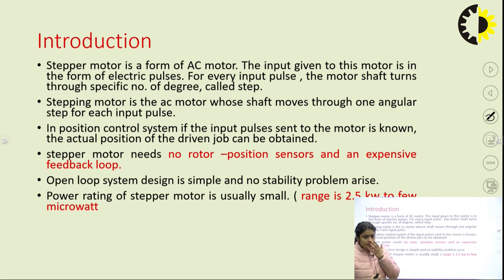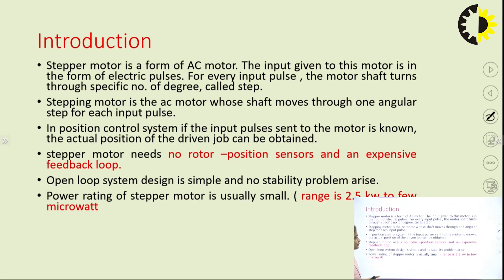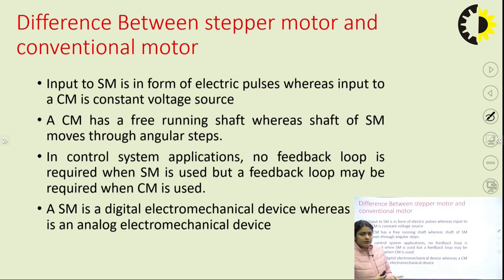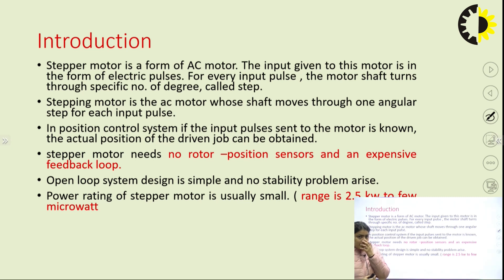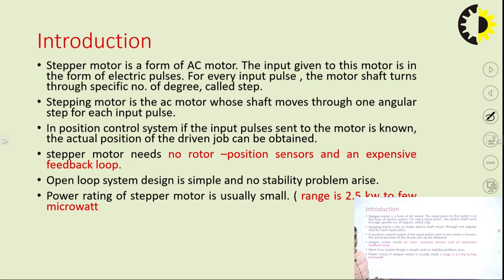The input to the stepper motor is in the form of pulses, and as we apply the pulses the motor rotates in steps. The stepping motor is an AC motor whose shaft moves through one angular step for each input pulse. In a position control system, if the input pulses sent to the motor are known, the actual position of the driven load can be obtained. This motor does not require any position sensor or feedback loop — it can work on a simple open loop system with no stability issues.